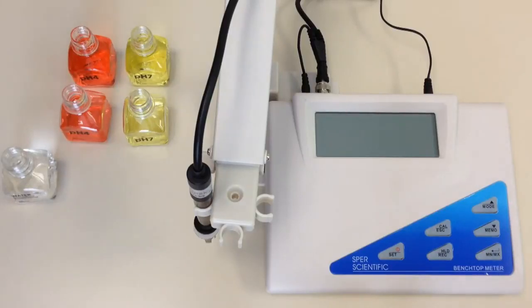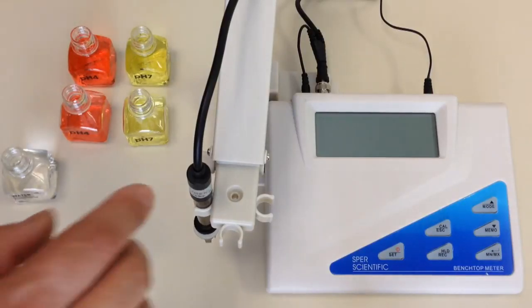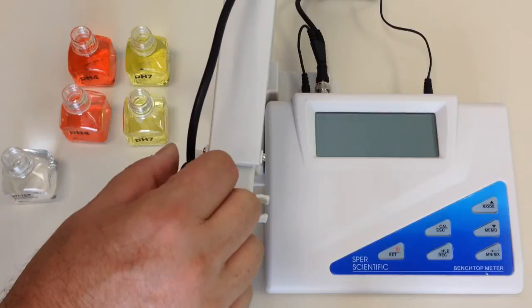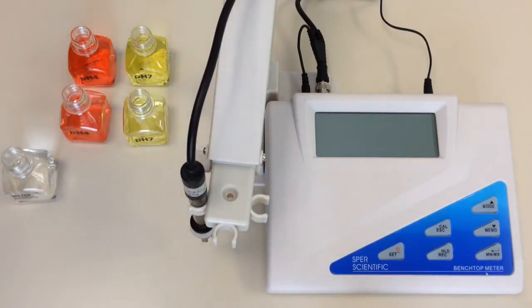Okay, today we are going to be showing you how to calibrate the Sper Scientific benchtop meter 860031 and how to handle the error 13 message. First of all, I want to point out that we are using a probe that comes with this particular benchtop that handles what's called ATC, or automatic temperature compensation. If you're not using a probe that does automatic temperature compensation, please follow the instructions in the manual.